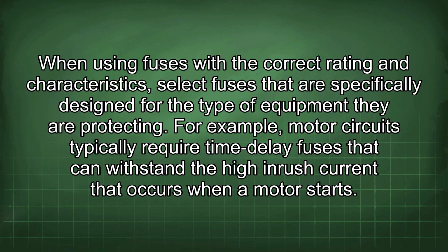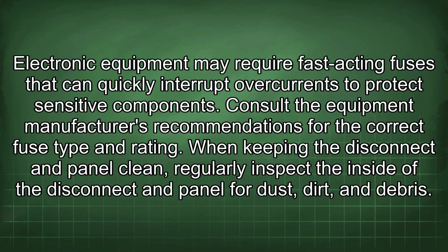When using fuses with the correct rating and characteristics, select fuses that are specifically designed for the type of equipment they are protecting. For example, motor circuits typically require time delay fuses that can withstand the high inrush current that occurs when a motor starts. Electronic equipment may require fast-acting fuses that can quickly interrupt overcurrents to protect sensitive components. Consult the equipment manufacturer's recommendations for the correct fuse type and rating.